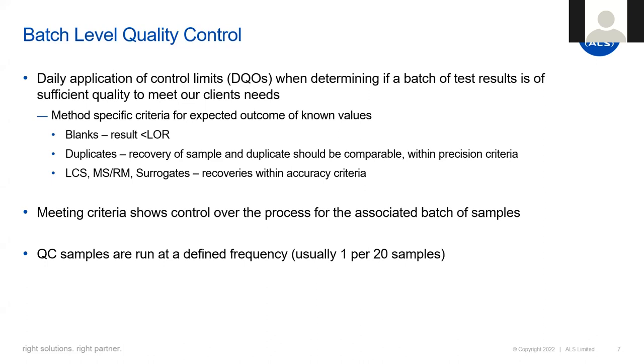Meeting the criteria shows everything is acceptable; however, what happens if there are exceedances? Common causes of DQO exceedances include sample matrix effects or chemical interferences impacting recovery, non-homogeneity of samples impacting precision, or equipment failures impacting recovery and turnaround times. If there is an exceedance, an investigation must be done: we investigate the situation, fix the problem, and re-analyze the samples if possible. When re-analysis is not possible, the lab can report the results, but they must be qualified with comments describing the potential impact. QC evaluation is the main defense against inappropriate data being reported.